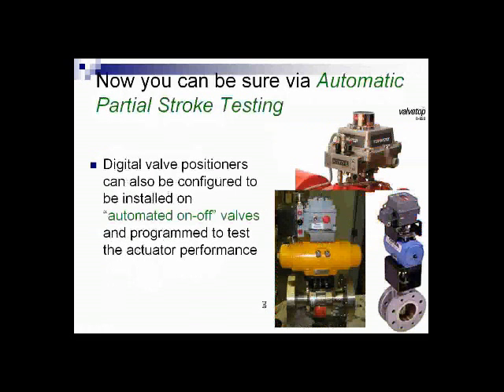There's a new technology out that's called partial stroke testing, and it actually is an automatic partial stroke testing. There's several companies that are making this. TopWorks, Fisher has it, Masoneilan has it. These are also called emergency shutdown apparatuses. They look like, or actually they are, a part of the digital valve positioner family that we spoke about earlier, the smart positioners. They actually have been adapted to be used in conjunction with a programmable logic controller to be able to test a regular on-off automated valve while it's in line, or while it's still running the process. So as it says here, these digital valve positioners can be installed on an automated on-off valve, and you can program them to test your actuator and your valve performance while everything is still running.